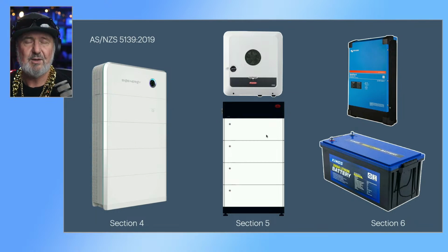Section 5 is where those are separate components. The battery system is a pre-assembled battery system. In this case, I'm showing a BYD HVM, I think it's an HVM, and a separate PCE, in this case the Fronius Gen 24. They're a very popular combination. I've got exactly that here at the lab. Looks like they even colour coordinated them. Section 5 really only applies to the battery system, because you are now installing DC cables between the pre-assembled battery system and the PCE, and therefore you've got to consider overcurrent protection, mechanical protection, isolation, quite a few extra things.